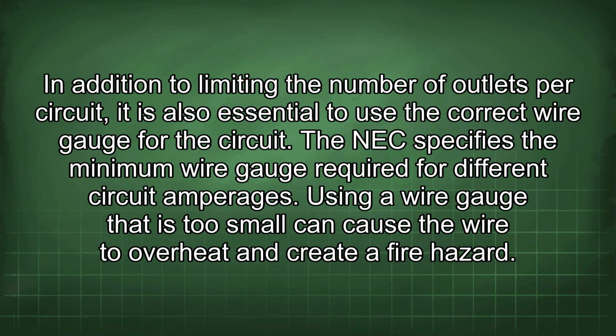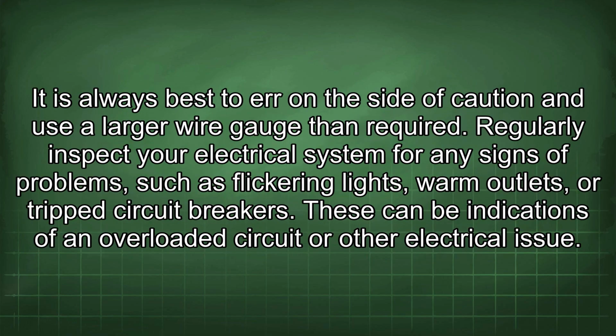In addition to limiting the number of outlets per circuit, it is also essential to use the correct wire gauge for the circuit. The NEC specifies the minimum wire gauge required for different circuit amperages. Using a wire gauge that is too small can cause the wire to overheat and create a fire hazard. It is always best to err on the side of caution and use a larger wire gauge than required.